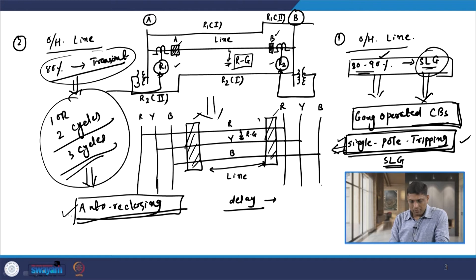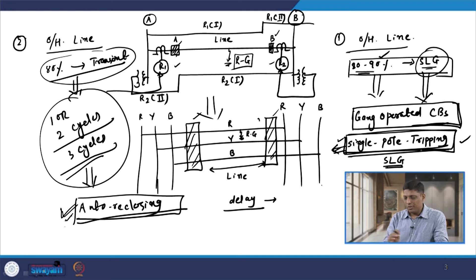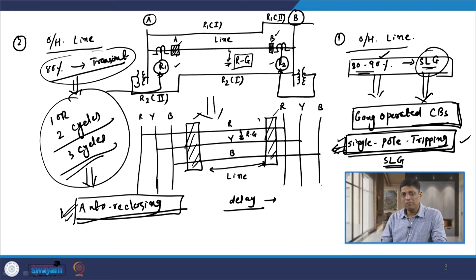So, if I wish to achieve the auto reclosing feature, then the distance relay again is not capable. So, we need to use some other philosophy, or we need to modify the conventional distance relaying philosophy, so that we can utilize the auto reclosing feature in the conventional distance relay. In the same way, if we want to utilize single pole tripping, then also we need to either modify or go for some other type of relaying scheme. So, these two are the major disadvantages of the distance relaying scheme, that is single pole tripping and the auto reclosing feature.